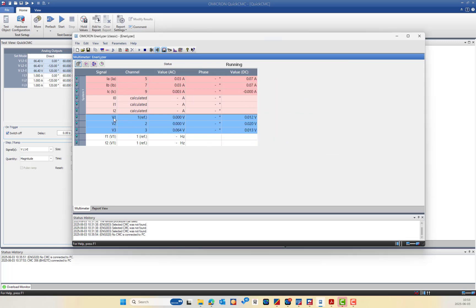After clicking OK, you can see V1, V2, V3, IA, IB, IC with magnitude and phase angle measurement, plus frequency measurement referenced to V1. Currently a weak signal error is showing because nothing is being injected — the device is offline.